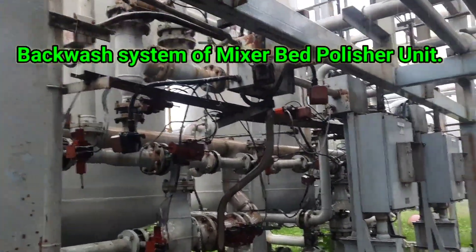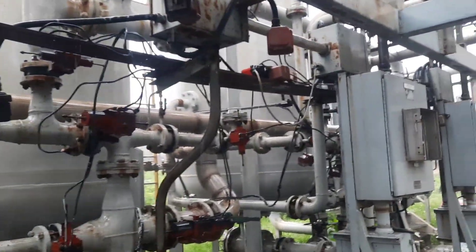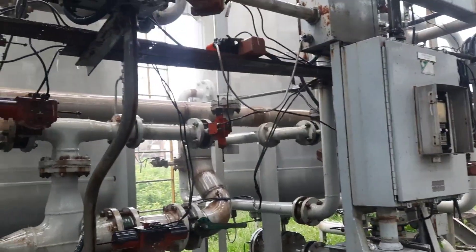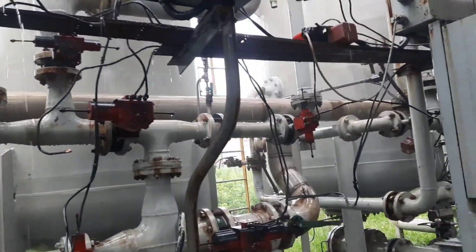For backwashing the mixed bed polisher unit, you have to open two KB valves — one inlet KB valve and one outlet KB valve. From the name 'backwash', you should understand it means reverse water flow, that is from the bottom side to the top side.